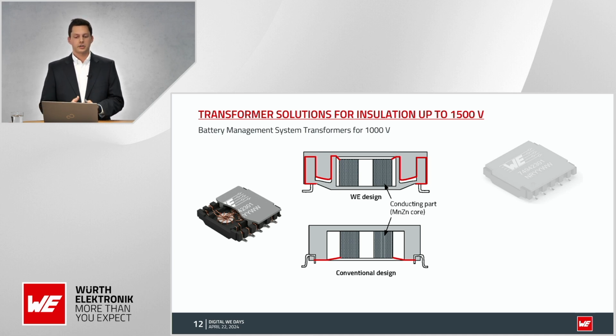As opposed to competitors, the required creepage distance is achieved without an additional coating exposed to ambient conditions such as dryness or heat. As can be seen in the picture on the left, our special housing design consists of two different parts, so we have an underlayer and an upper layer. But for sure, the final product is of course a single component. This is for illustration purpose only.